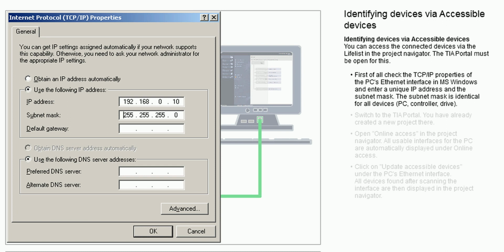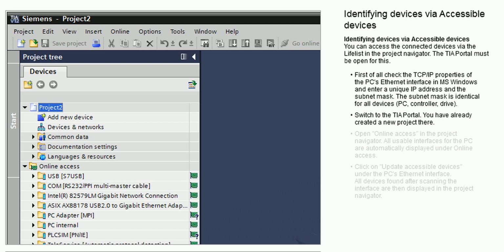First of all, check the TCP IP properties of the PC's Ethernet interface in MS Windows and enter a unique IP address and the subnet mask. The subnet mask is identical for all devices: PC, controller, drive. Switch to the TIA portal. You have already created a new project there.